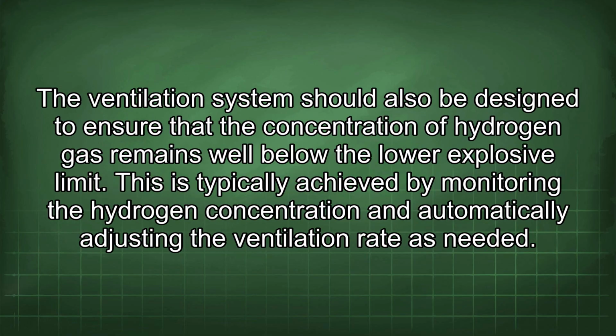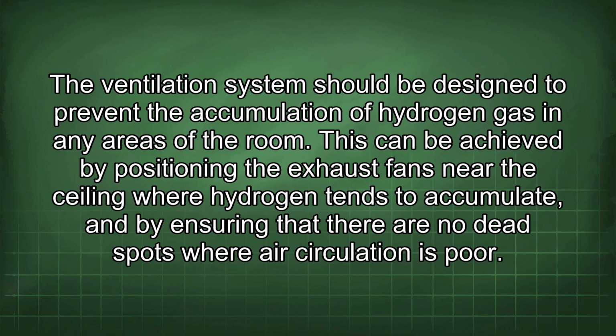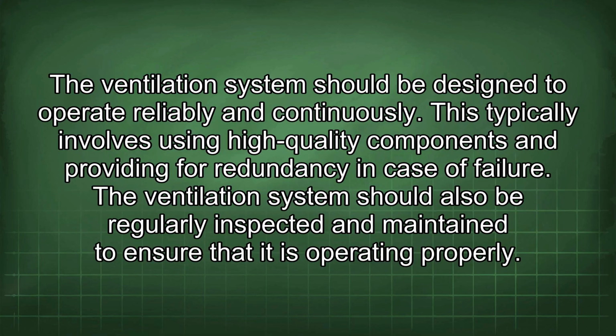The ventilation system should also be designed to ensure that the concentration of hydrogen gas remains well below the lower explosive limit. This is typically achieved by monitoring the hydrogen concentration and automatically adjusting the ventilation rate as needed. The ventilation system should be designed to prevent the accumulation of hydrogen gas in any areas of the room. This can be achieved by positioning the exhaust fans near the ceiling where hydrogen tends to accumulate, and by ensuring that there are no dead spots where air circulation is poor. The ventilation system should be designed to operate reliably and continuously. This typically involves using high-quality components and providing for redundancy in case of failure.